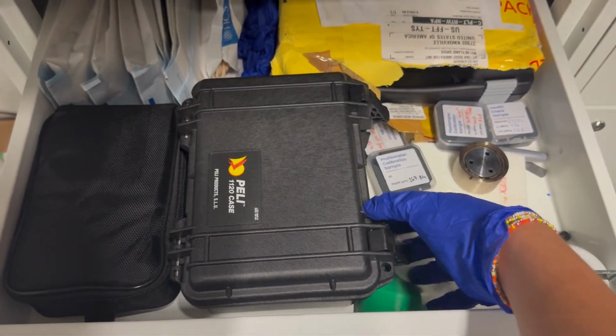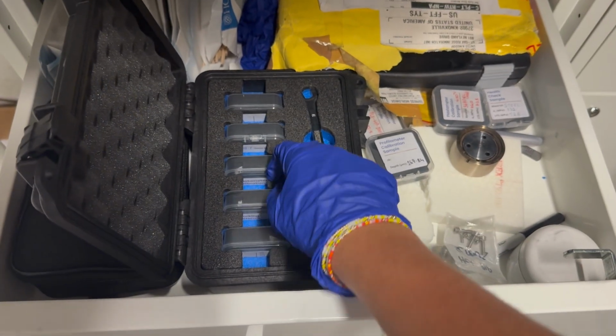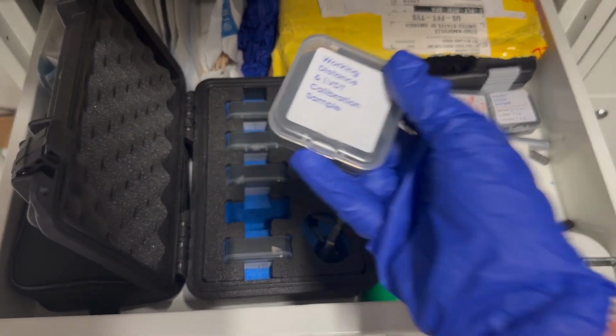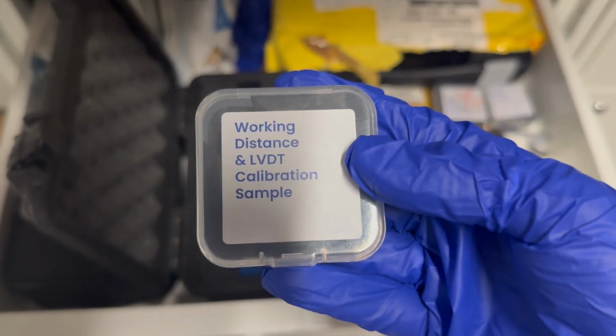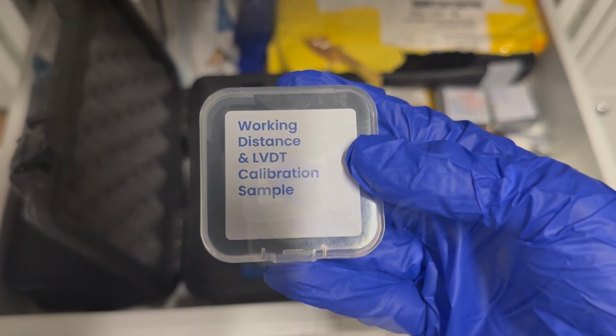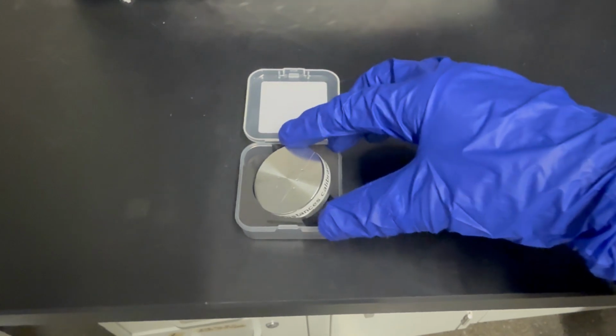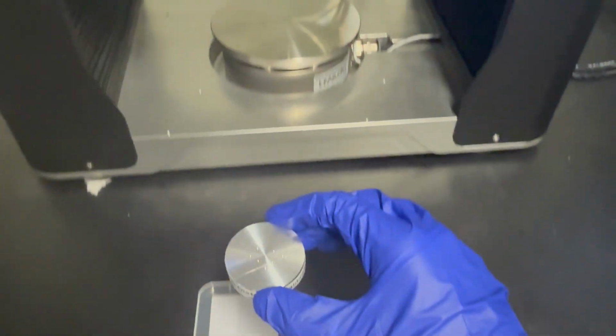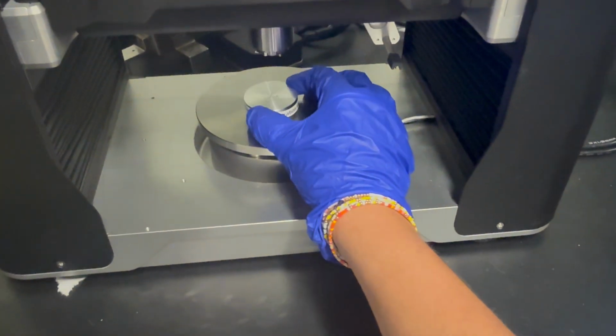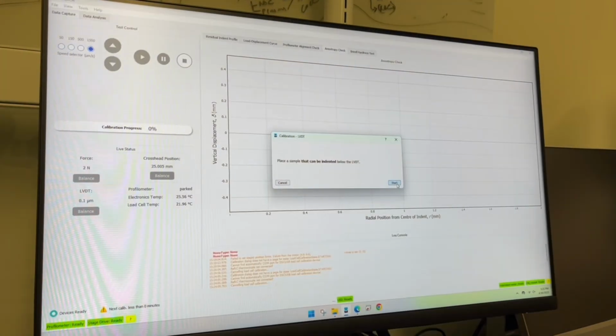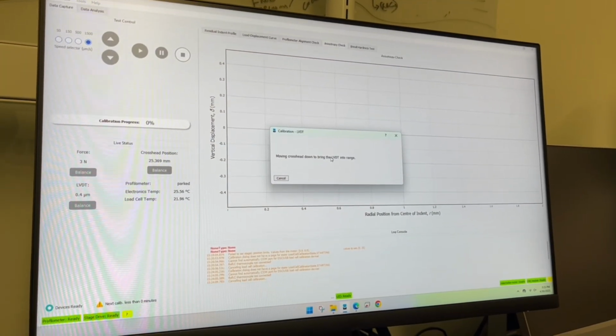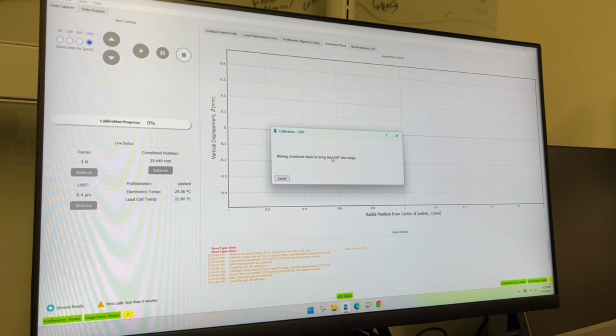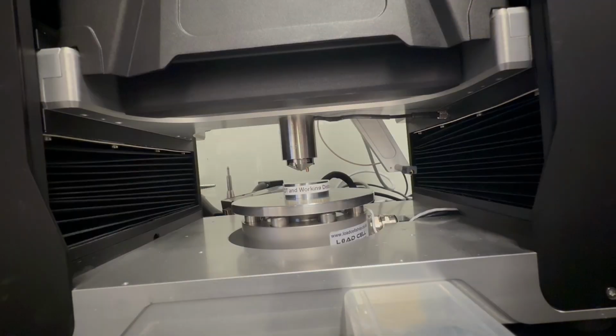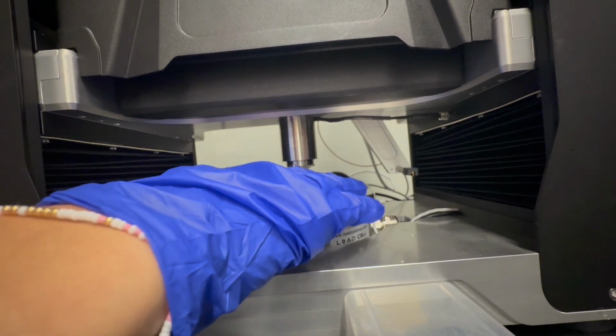Now it'll prompt you to get the sample, which you can find in the drawer. You want the one labeled Working Distance and LVDT calibration. And then you can go ahead and place it onto the plate beneath the indenter. And now you're ready to start the machine setup. So essentially, it's going to perform several different calibrations, including working distance, LVDT, and profilometer distance calibrations.